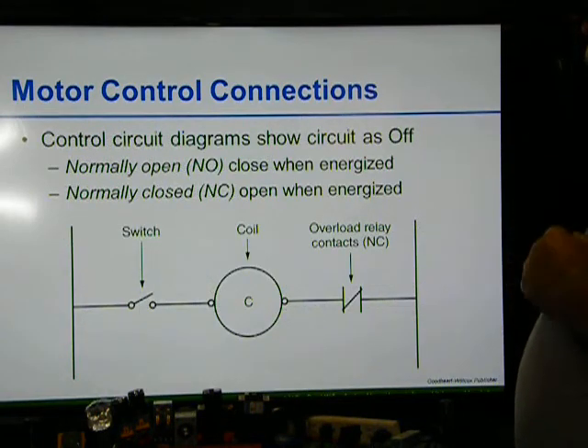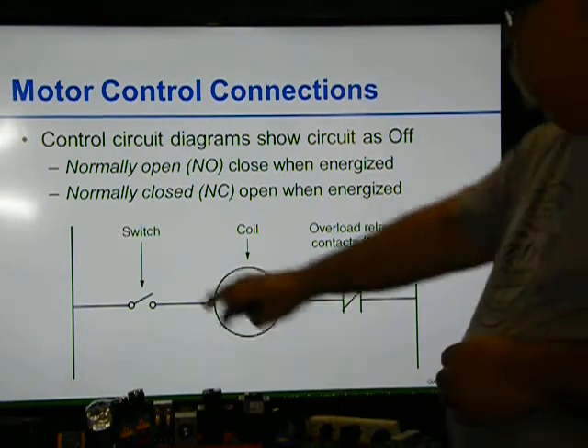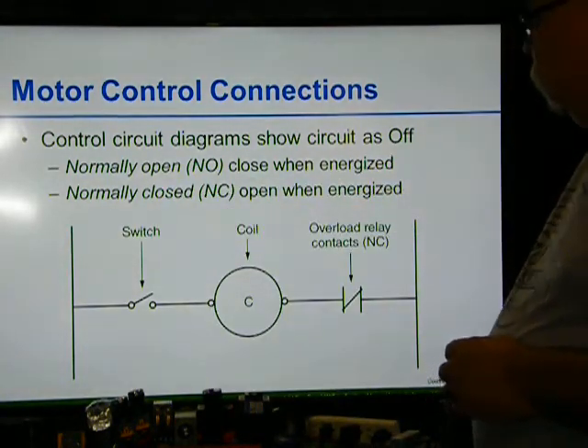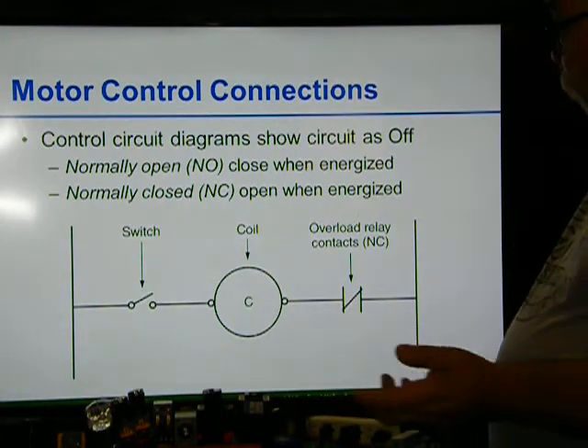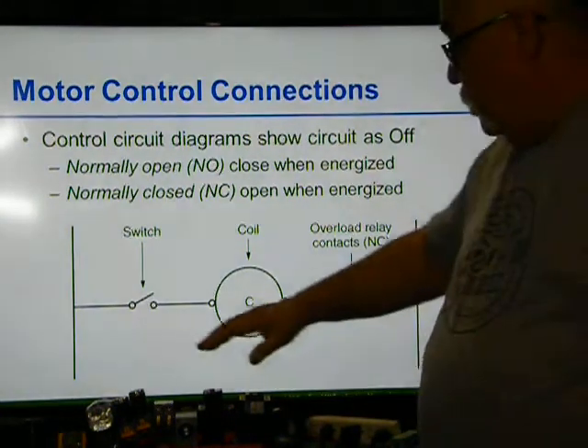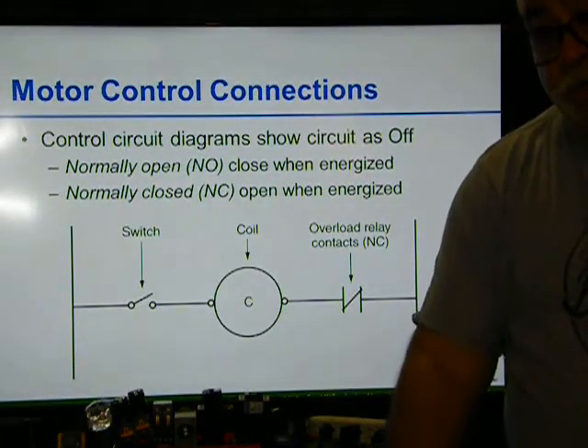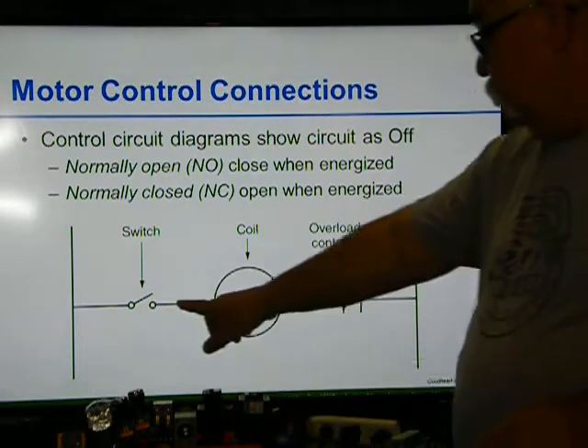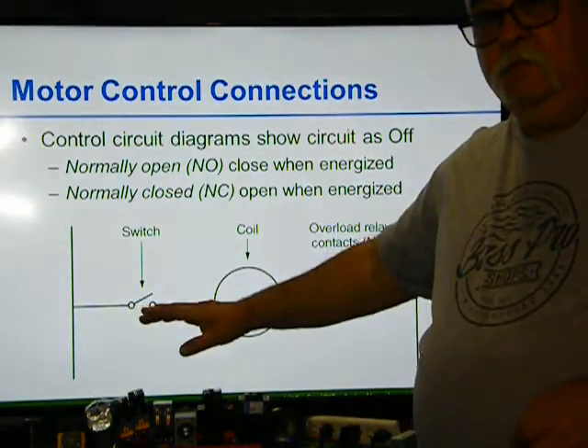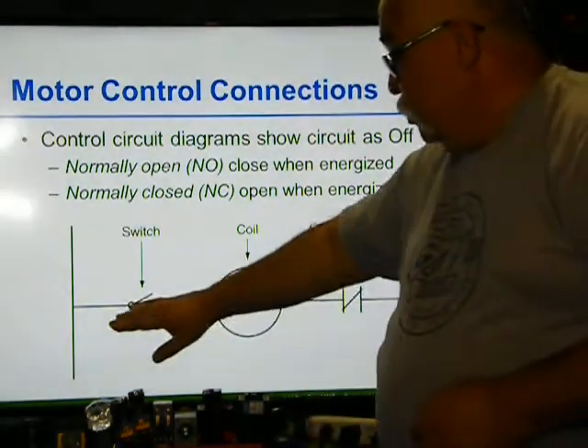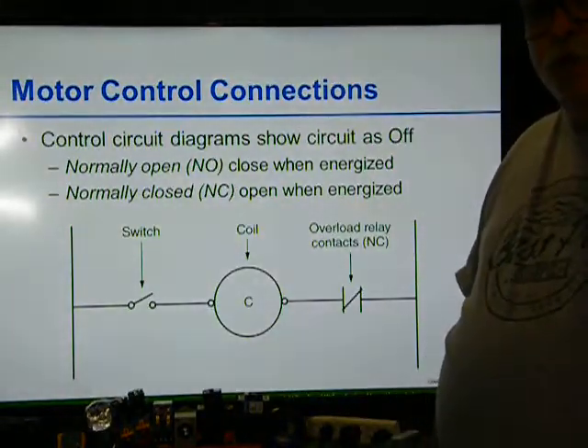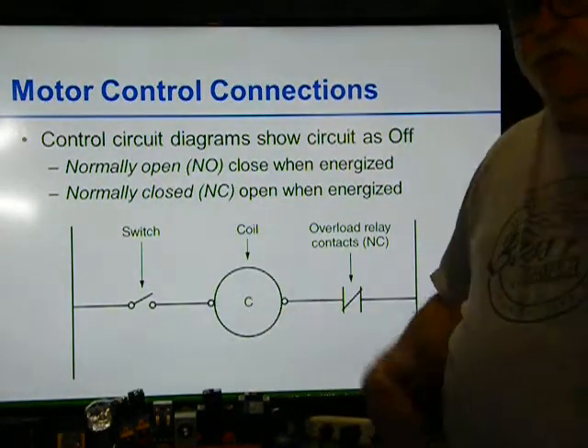Motor control connections. A control circuit diagram shows the circuit as off. That's what I was talking about. So normally open closes when energized. Normally closed opens when energized. So again, this one is normally open. This one is considered normally open because the switch is always open, so it doesn't work until I close it. Okay. Now when I have it at normally closed, this switch would be on, but when I open the switch, it comes on. So it works in reverse.